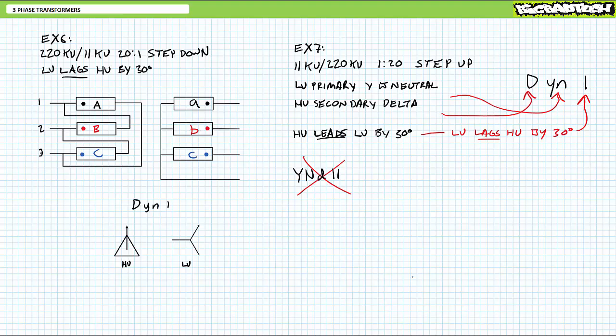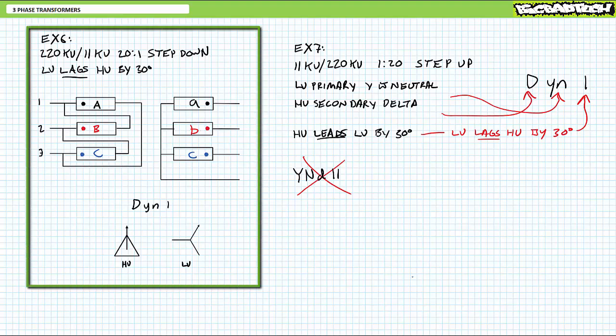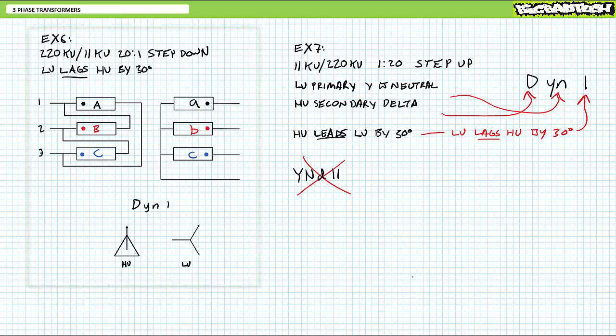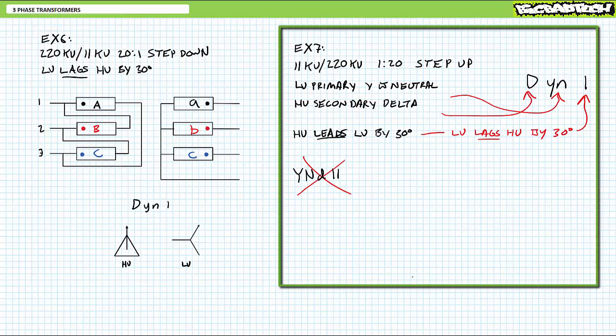The exact same designation as our previous example, only it's being run in reverse. Does this or does this not make sense? If you've been paying attention to the standard nomenclature format, it does make sense because transformers are bi-directional in nature. A 20 to 1 step-down transformer with a delta-configured high-voltage primary input and a Y-configured low-voltage secondary output, where low-voltage output lags high-voltage input by 30 degrees, i.e. a DYN1, is a 1 to 20 step-up transformer with a Y-configured low-voltage primary input and a delta-configured high-voltage secondary output, where high-voltage output leads low-voltage input by 30 degrees, i.e. also DYN1.